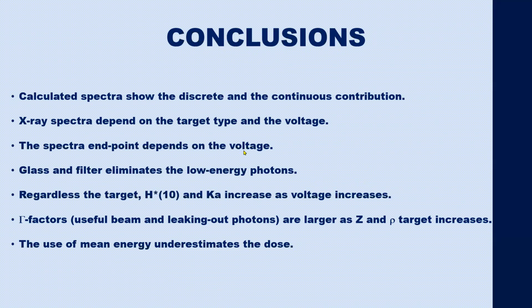So as conclusions, we can point out that the calculated spectra show both contributions, the discrete and the continuous. Also, the X-ray spectra depend on the target type and the voltage, and the spectra endpoint depends on the voltage that we use. The glass and the filter eliminate in a large amount the low energy photons that do not contribute to the image, and that could reach the skin and produce serious damage, because having low energies, all these photons will be absorbed in the patient's skin. So the use of glass and filters eliminates these undesirable low energy photons.